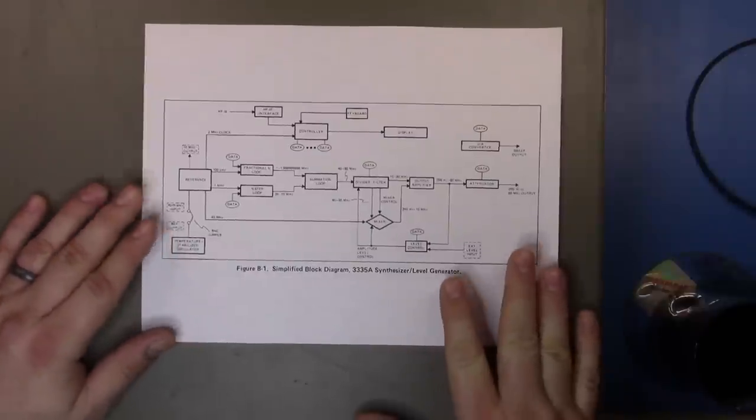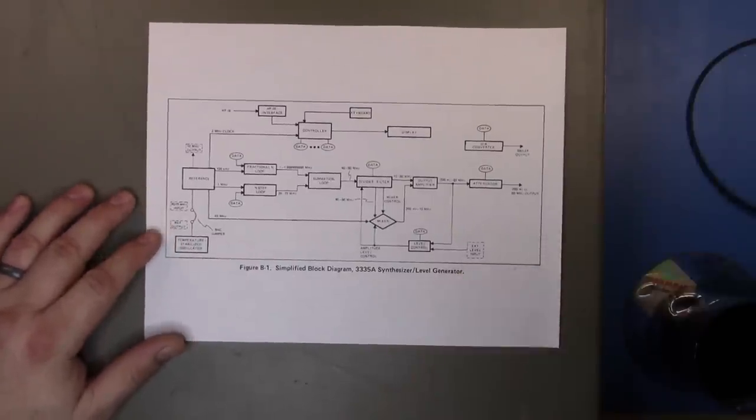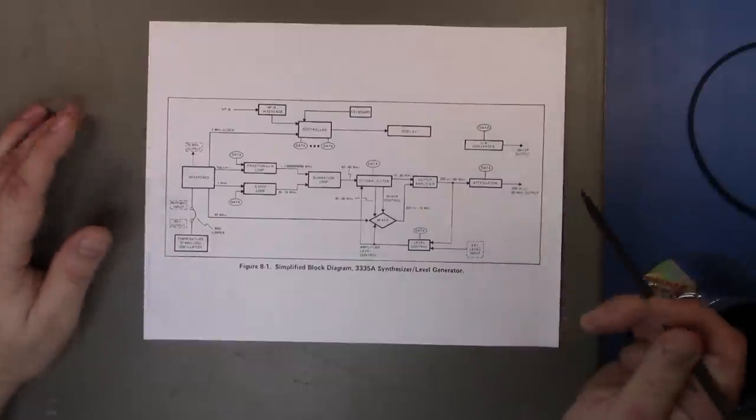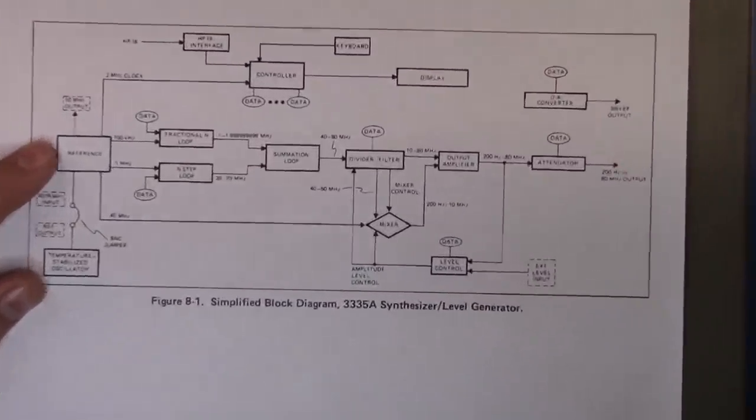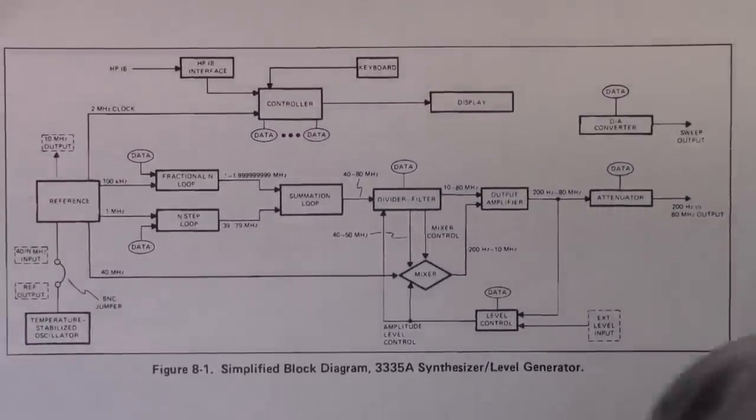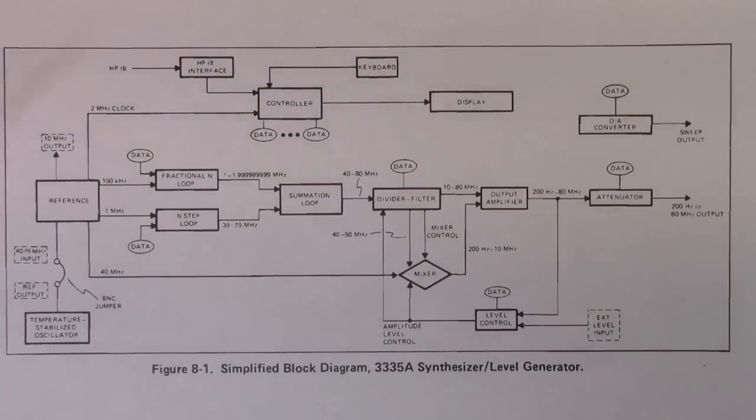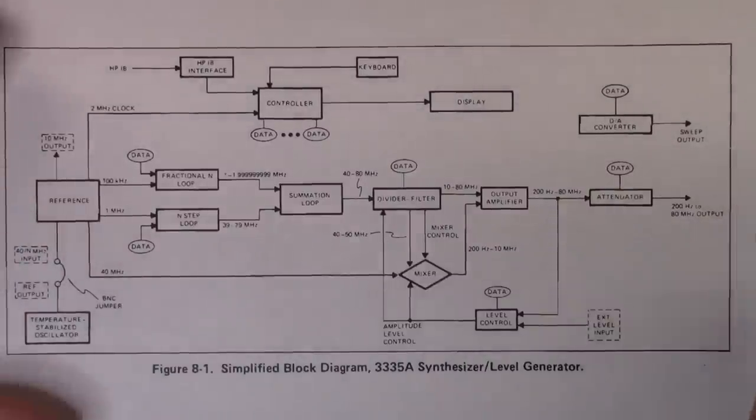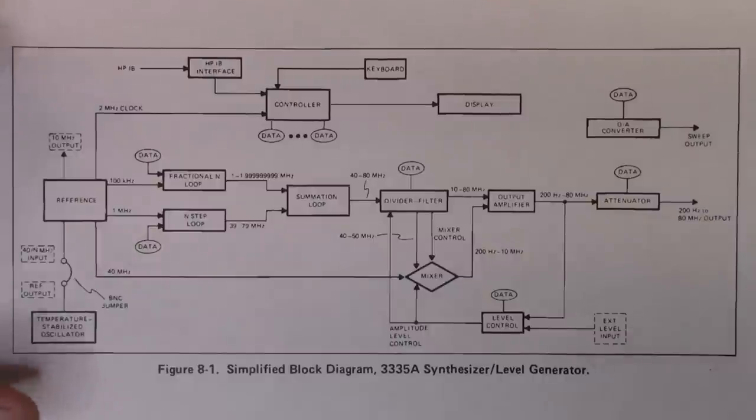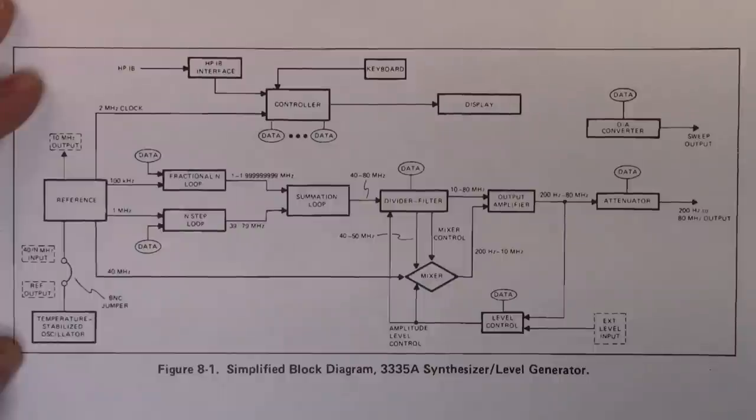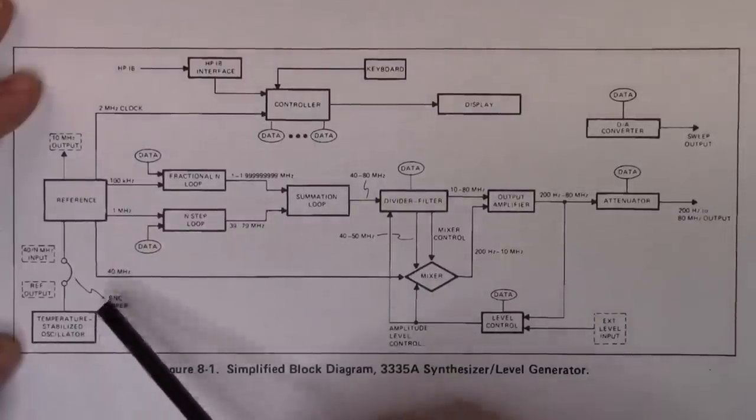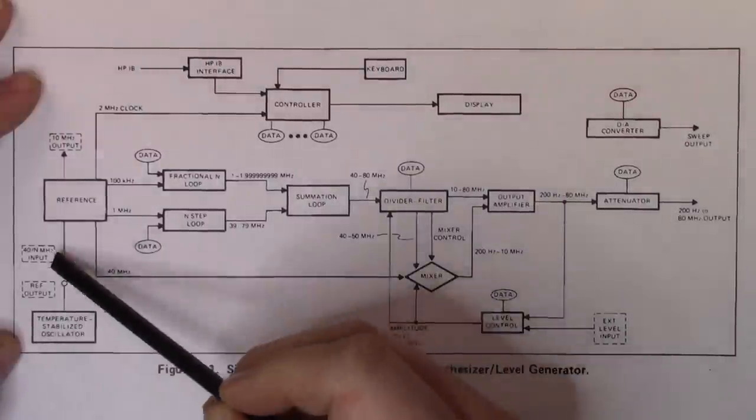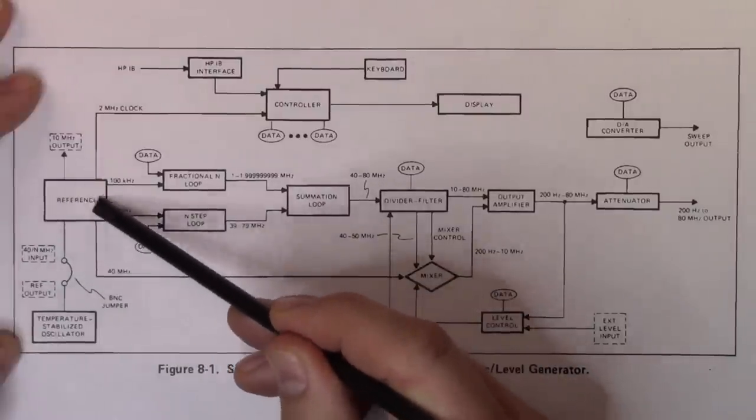And now we're ready to take a look inside this unit. But before we do that, I thought we might just take a look at the block diagram and get an idea of how the system works. So let me zoom in a little bit so we can see the block diagram a bit better. The drink of choice today is a nice Washington State red wine. What we have here is the temperature stabilized oscillator which is in the unit.